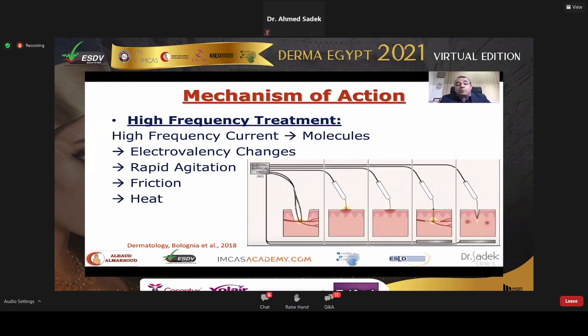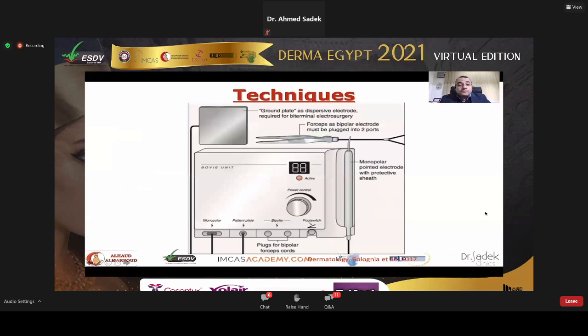And this has been used for many purposes. As we see in the image, this is the bipolar coagulation, and this one is the electrofulguration, where the tip of the device does not touch the skin and covers a superficial lesion of larger diameter, and then the electrodesiccation, which touches the skin. The electrocoagulation goes with this tip, which is like a metallic ball, causing coagulation of blood vessels which are not deep in the skin, and then the electrocutting or section, as the one used in surgeries.